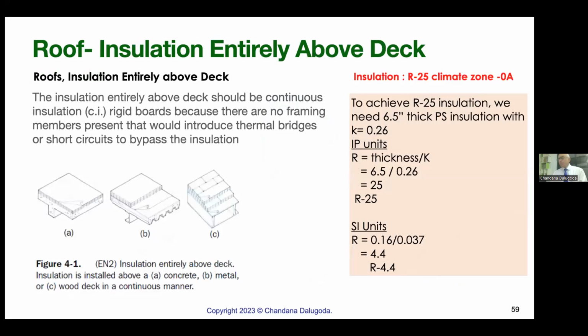Roof insulation, I'm not going to go through all these, but for a roof insulation entirely above deck, we need insulation R25 for climate zone 0A. R25 is in inch pound. To achieve R25 insulation, we need 6.5 inches thick polystyrene insulation. 6.5, mind you, not 1 inch. You need about 6 inches. Do you really use insulation over the above deck? I don't think you do. Not in Sri Lanka. But for a net zero building, you need minimum 6.5 thick polystyrene insulation.